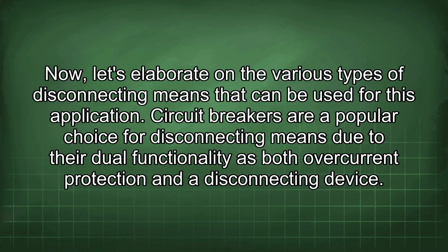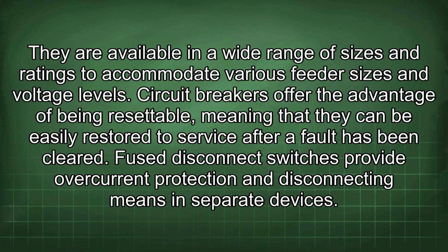Circuit breakers are a popular choice for disconnecting means due to their dual functionality as both overcurrent protection and a disconnecting device. They are available in a wide range of sizes and ratings to accommodate various feeder sizes and voltage levels. Circuit breakers offer the advantage of being resettable, meaning that they can be easily restored to service after a fault has been cleared.